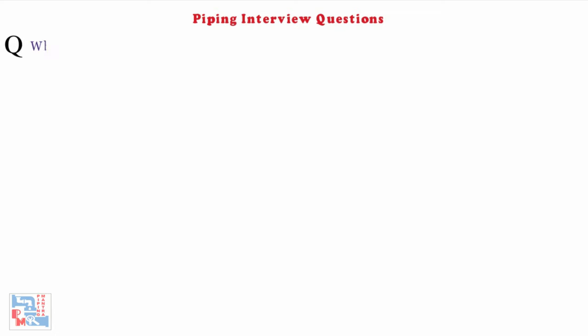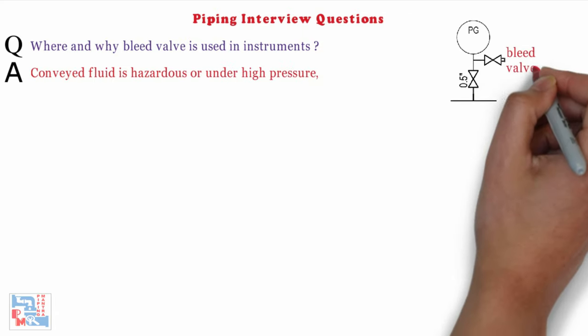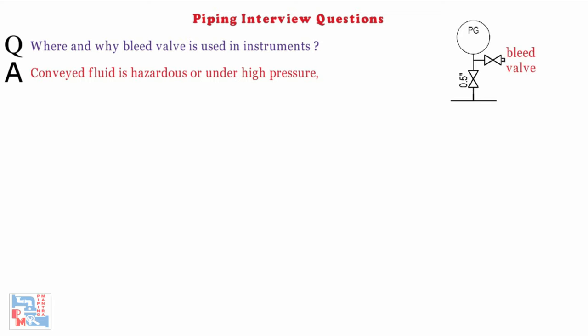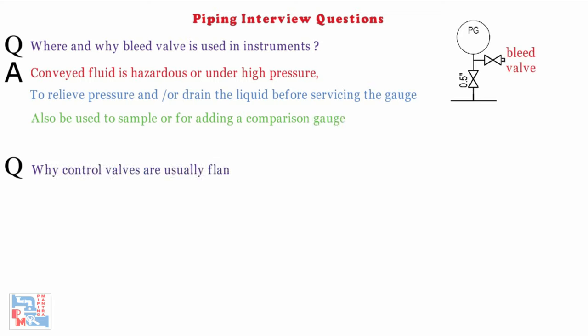Next: where and why is a bleed valve used? If the conveyed fluid is hazardous or under high pressure, a branch fitted with a bleed valve is inserted between the gauge and its isolating valve to relieve the pressure and/or drain the liquid before servicing. It can also be used to sample or for adding a comparison gauge.